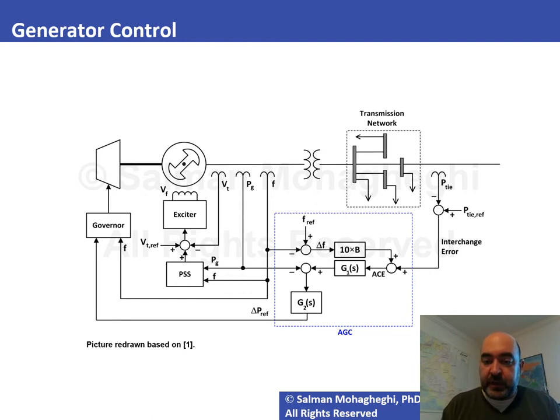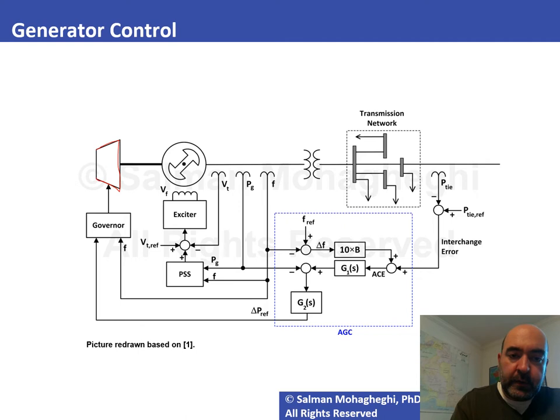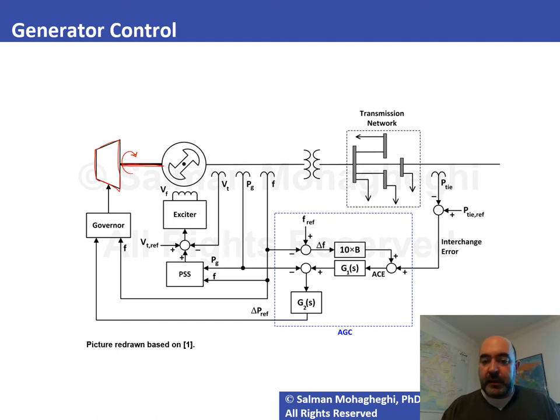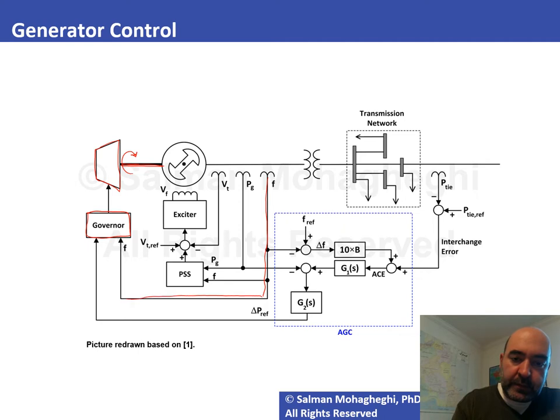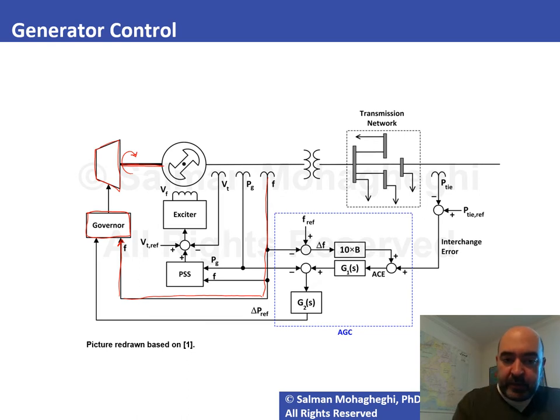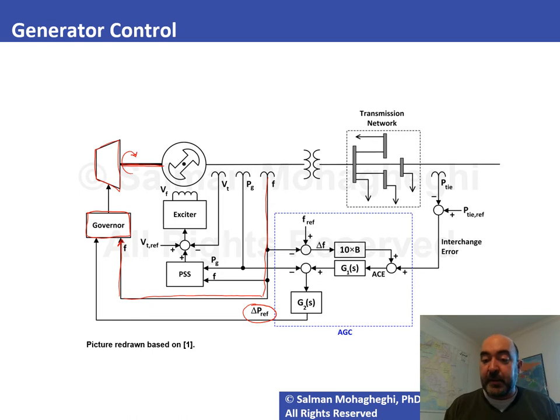This is how the controllers of a generator look and relate to one another. The turbine is the prime mover, mounted on the same shaft as the rotor. By rotating the turbine, we rotate the generator rotor and generate voltage at a particular frequency. The governor system monitors frequency at the terminals and adjusts the prime mover's rotational speed based on whether frequency is high or low. It also receives Δ P_ref — changes to the active power set point — from the AGC system.